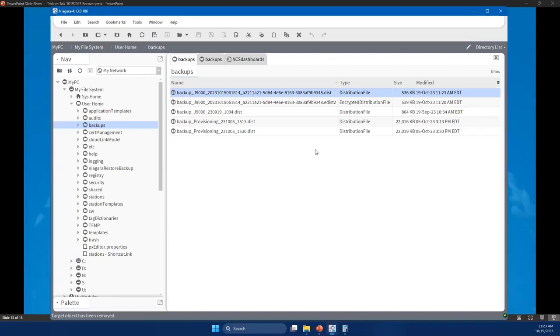Okay, so that's pretty much in a nutshell how the service gets installed, and how the subscription automatically appears if it's enabled. It defaults to every Sunday plus or minus an hour, and backs up automatically. I can log into the Niagara Cloud Suite portal, look at those backups, put comments on those backups, protect one to keep forever if that was the baseline of the building, and download it to restore it. And I'll send it back to Nicole.